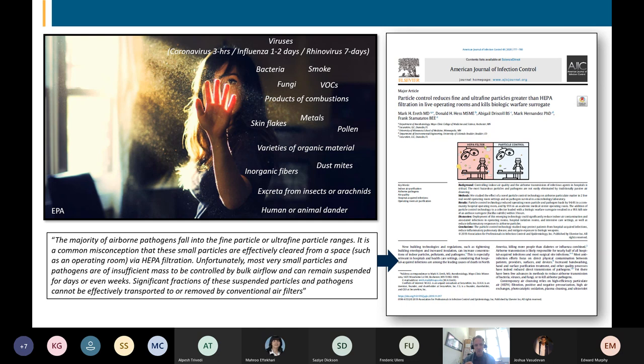They concluded in the article that the majority of airborne pathogens in the air, the stuff that we're talking about in the sunbeam that you can't see and you can see but can cause detrimental effects to human beings, are what are considered fine and ultrafine particles. They said it's a common misconception that these small particles are effectively cleared from a space, even a hospital operating room, even using HEPA filtration. Now, HEPA filtration is 99.97% efficient at removing particles of 0.3 micrometers in size, and then more efficient removing both smaller and larger particles. Unfortunately, most very small particles and pathogens, they tell us, are of insufficient mass, size, weight to be controlled by what they call bulk airflow, but it's just traditional air movement and velocities that we see in the built environment, and can remain suspended for days or even weeks.